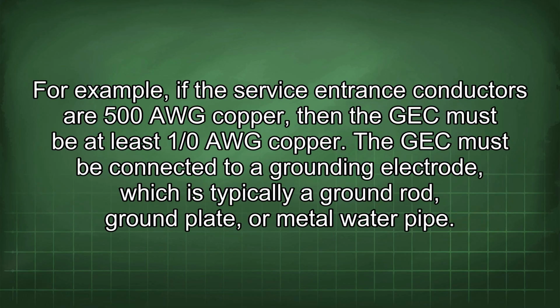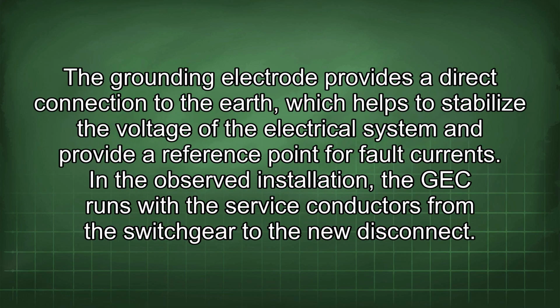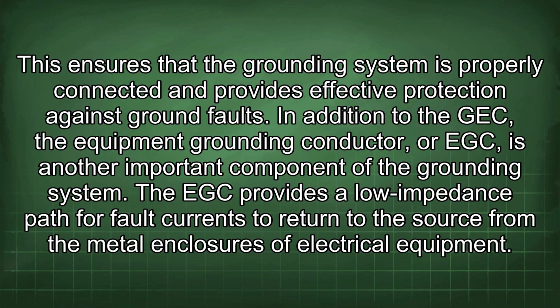For example, if the service entrance conductors are 500 AWG copper, then the GEC must be at least 1/0 AWG copper. The GEC must be connected to a grounding electrode, which is typically a ground rod, ground plate, or metal water pipe. The grounding electrode provides a direct connection to the earth, which helps to stabilize the voltage of the electrical system and provide a reference point for fault currents. In the observed installation, the GEC runs with the service conductors from the switchgear to the new disconnect. This ensures that the grounding system is properly connected and provides effective protection against ground faults.